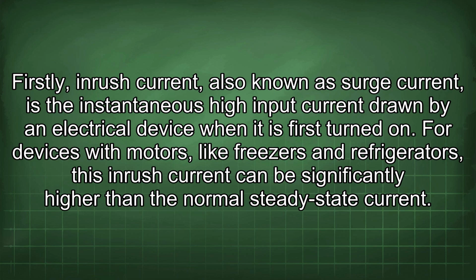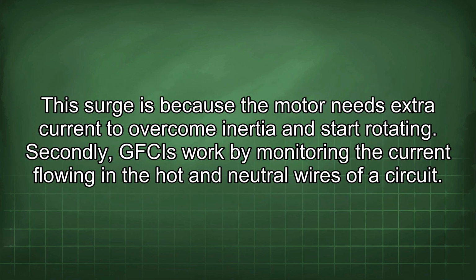Firstly, inrush current, also known as surge current, is the instantaneous high input current drawn by an electrical device when it is first turned on. For devices with motors like freezers and refrigerators, this inrush current can be significantly higher than the normal steady-state current. This surge is because the motor needs extra current to overcome inertia and start rotating.